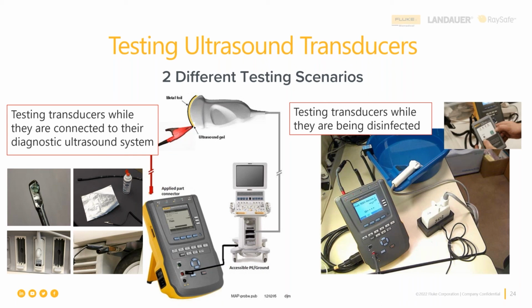So we need to make this measurement, whether it's while it's connected to its diagnostic ultrasound system, or else during cleaning. The standard of care for transesophageal echocardiograph transducers and other diagnostic ultrasound transducers is that they should be cleaned between each patient use. And while they're being cleaned or disinfected, that's a perfect time to run these tests, because if the jacket has been bitten through, the bite through will allow the ingress of the cleaning solution, which is conductive, and that will provide short circuits inside the transducer. Not a good thing. So we will do testing of that transducer while it's being disinfected.